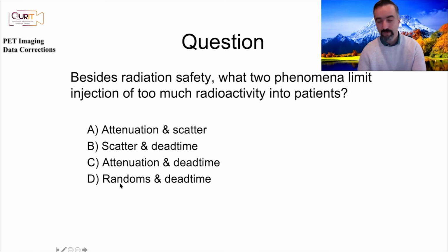But randoms, because of that quadratic relationship, really do increase more percentage-wise. And also dead time just kills more and more events, especially if it's paralyzable. Even in non-paralyzable, after some point, it's pointless to increase the radioactivity.